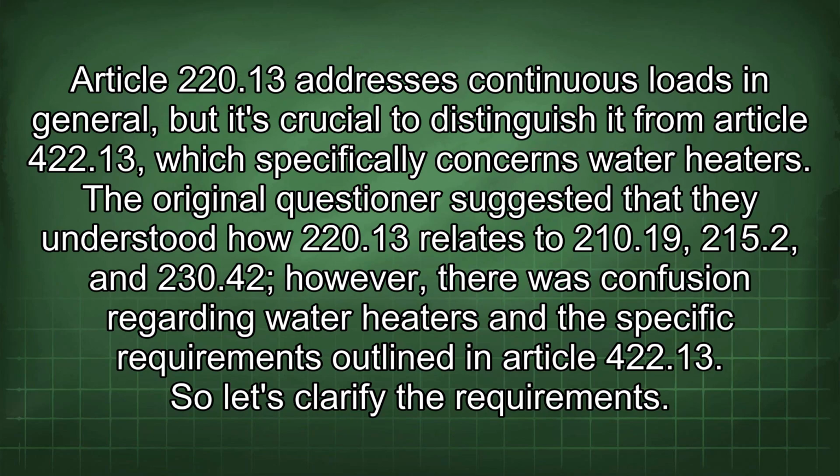Article 220.13 addresses continuous loads in general, but it's crucial to distinguish it from Article 422.13, which specifically concerns water heaters. The original questioner suggested that they understood how 220.13 relates to 210.19, 215.2, and 230.42. However, there was confusion regarding water heaters and the specific requirements outlined in Article 422.13. So let's clarify the requirements.